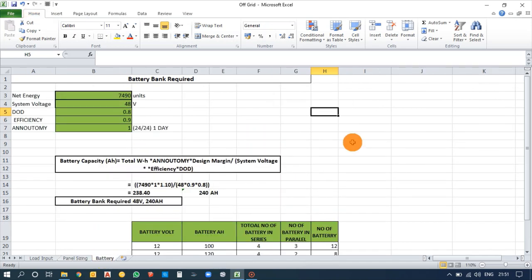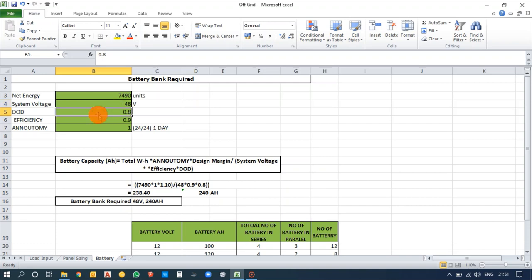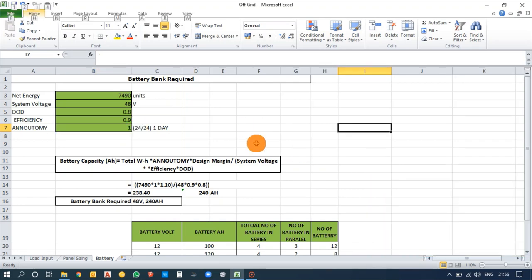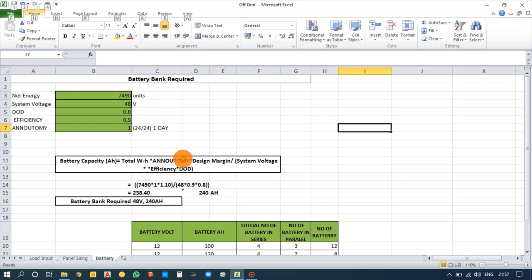For battery calculation, the variables are: system voltage (the inverter voltage), DoD (depth of discharge — the maximum point the inverter can discharge), efficiency of the inverter, and autonomy — how many days of backup you need. One day of autonomy is 24 hours; for two days, use a value of 2. The design margin is normally taken as 1.10 for safety.